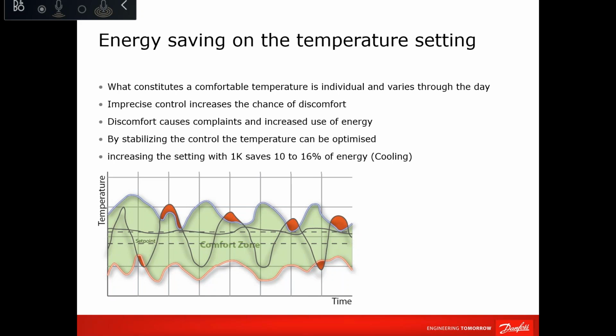This exercise we did in one of the hotels, and it was like 2 degrees. The effect was huge. Why? Because they have like 30% of the hotel as common areas, and in those common areas there was no control at all. It was linked with BMS, but the actuator is not working, the valve is kept at full open, the control is only on the fan. Some of them are set to 19 degrees in corridors, etc.